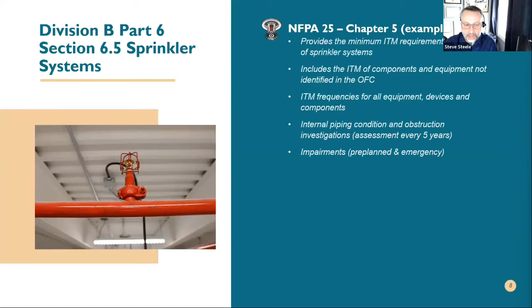Unfortunately with ITM, the more you exercise the system, the more detrimental it can be. What I mean is if you have a water-based system and you introduce air into the system through flow testing and main drain tests, you have to be very diligent in getting that air out—a qualified person venting that air—because you may affect the longevity of the pipe and have issues with it. But within the document, you are checking that on an ongoing basis. So even though they are being exercised, if they're prone—especially the lighter wall pipe, that Schedule 5 pipe that was put in through the 90s—you get that assessment, or at least you're keeping your finger on the pulse for that.